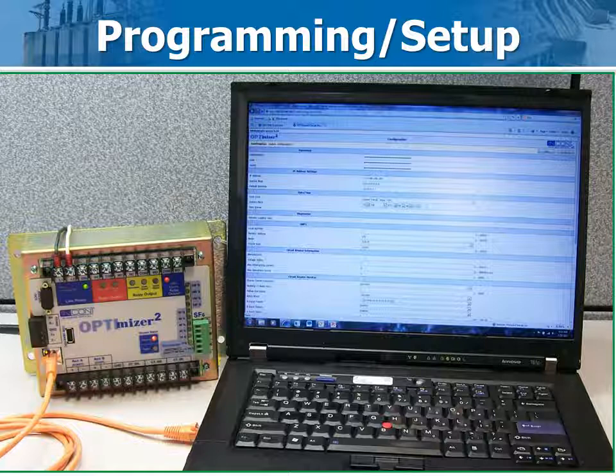Setup is easy. The best way to program multiple optimizer 2 units that are being installed on the same breaker type is to use a thumb drive USB memory stick. A memory stick library can be created covering breaker models of interest. This saves a huge amount of setup time and makes the whole process easy and straightforward.